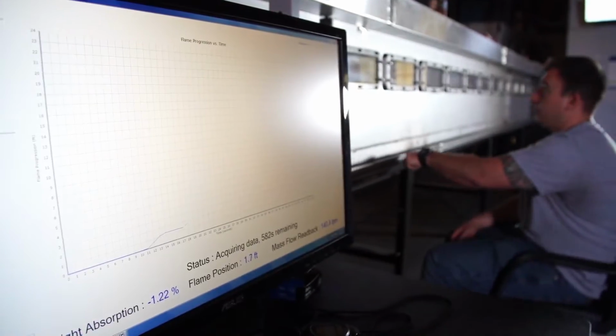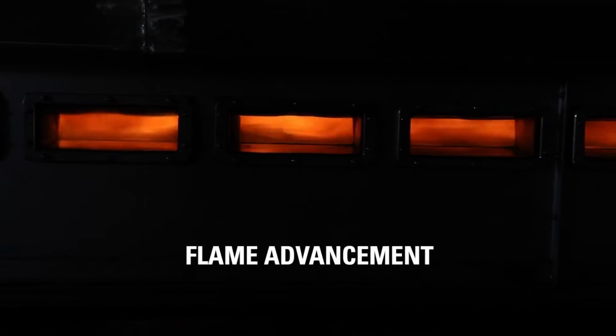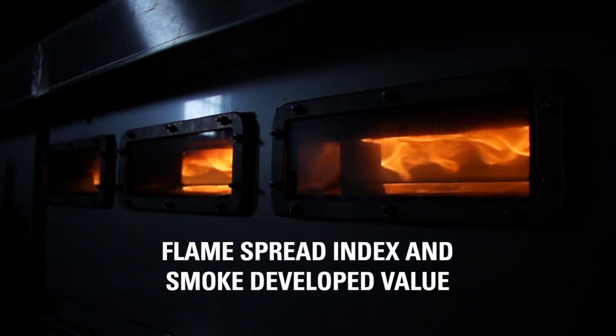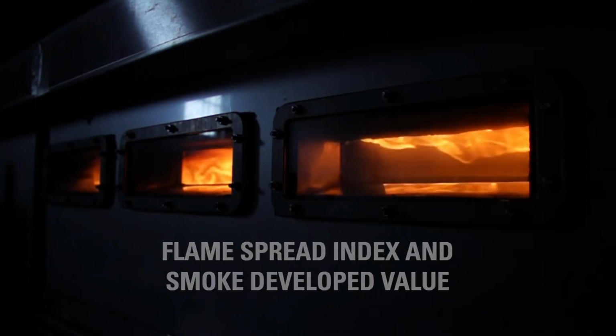During the test, a technician continually records flame advancement through the tunnel's observation windows, while the photometric instrumentation in the exhaust duct records the specimen's smoke developed. The 10-minute ASTM E84 test establishes the specimen's flame spread index and smoke developed index.